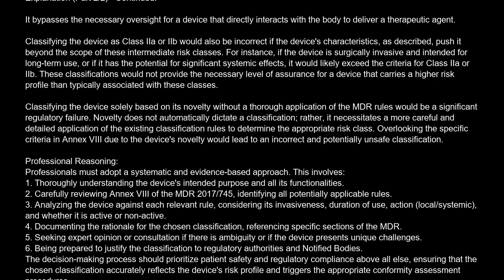This involves: 1. Thoroughly understanding the device's intended purpose and all its functionalities. 2. Carefully reviewing Annex VIII of the MDR 2017/745, identifying all potentially applicable rules. 3. Analyzing the device against each relevant rule, considering its invasiveness, duration of use, action local/systemic, and whether it is active or non-active. 4. Documenting the rationale for the chosen classification, referencing specific sections of the MDR.